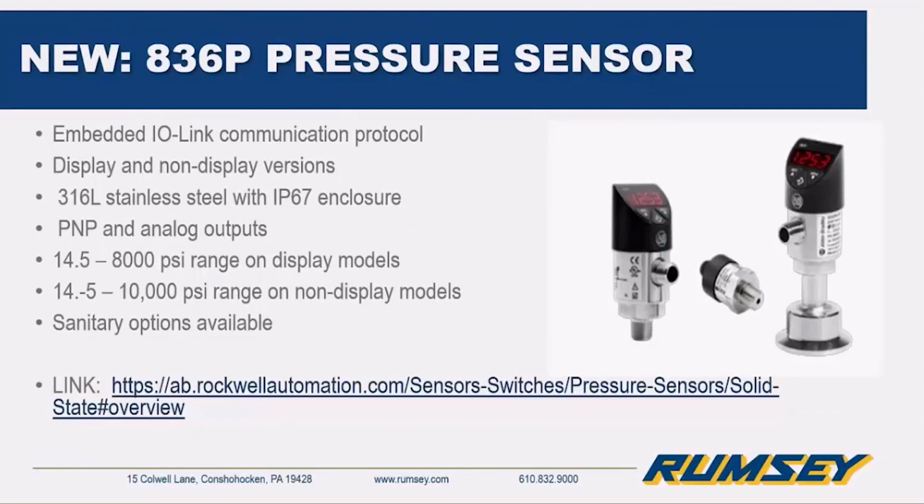And the last sensor I wanted to go over is the 836P pressure sensor, and I can also put the same requirements in for the 837T temperature sensor. They're both IO-Link enabled. They both have display and non-display versions. They're 316L stainless with an IP67 enclosure. They both have PNP and analog outputs. The pressure can go up to 8,000 psi, and the non-display pressure can go up to 10,000 psi, and sanitary options are also available. The temperature 837T also has 25 to 350 millimeter probes, and its temperature range is -20 to 80 degrees C. And they both have PNP and 4 to 20 analog outputs.